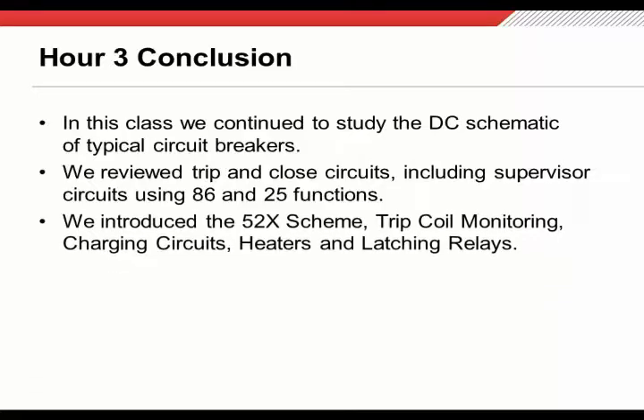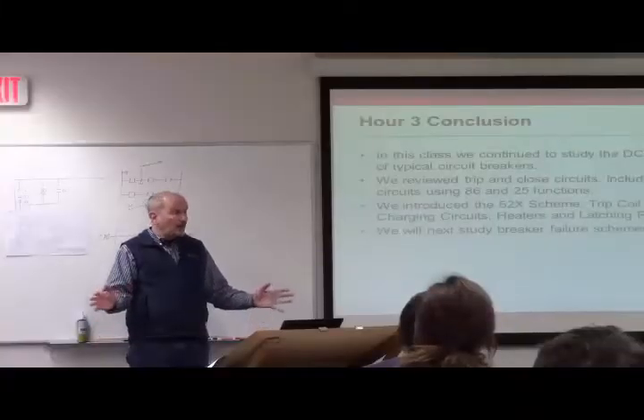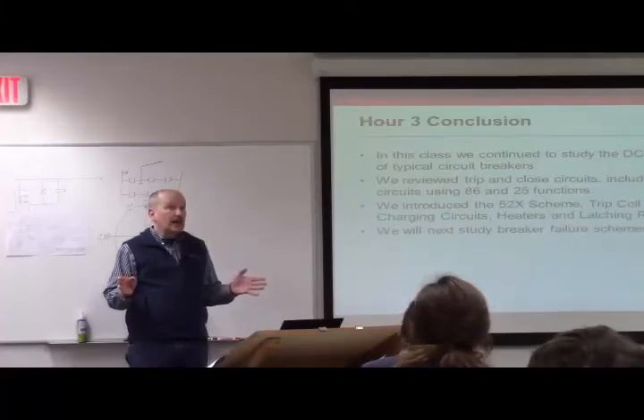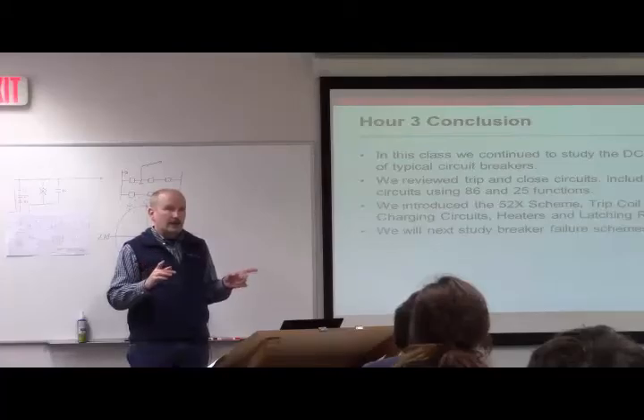In this class, we've spent a fair amount of time going through the DC schematic of a typical circuit breaker. We started with where we had been last week and then added a layer of detail on that. And we also spent some time talking about some features of our trip and close circuits that actually aren't in the circuit breaker, but they're back in the control building. We also introduced a couple other features including trip coil monitoring, charging circuits, heaters, and then we talked about the latching relay. And next week, we are going to kind of wrap up our study of circuit breakers. And we're going to talk about breaker failure schemes. Breakers are incredibly important within the power grid. But occasionally, despite our best efforts, they don't work. And it is not okay to have a breaker not open if something didn't work and not clear a fault. And that's what breaker failure schemes are all about, and we will get into that next week. Alright, thank you.